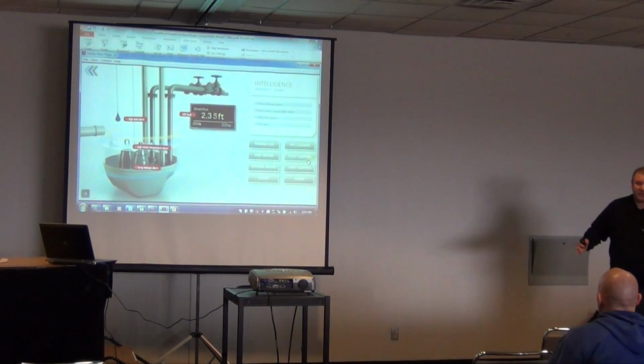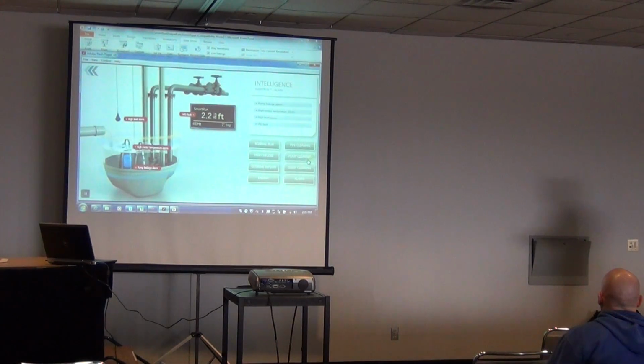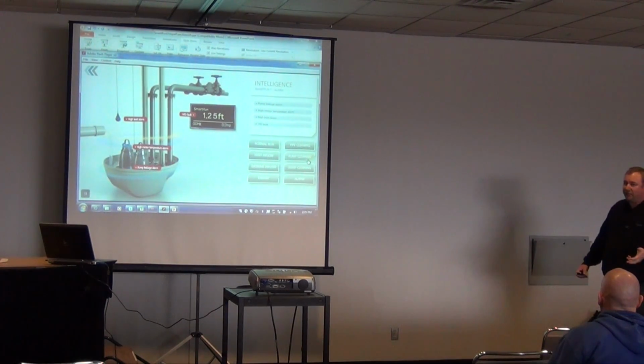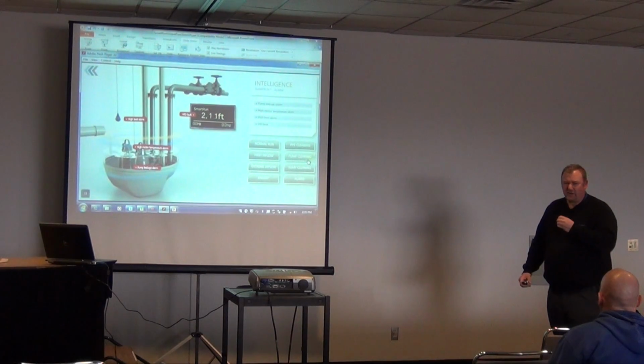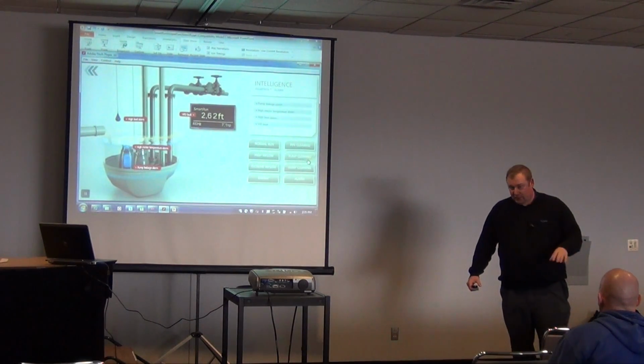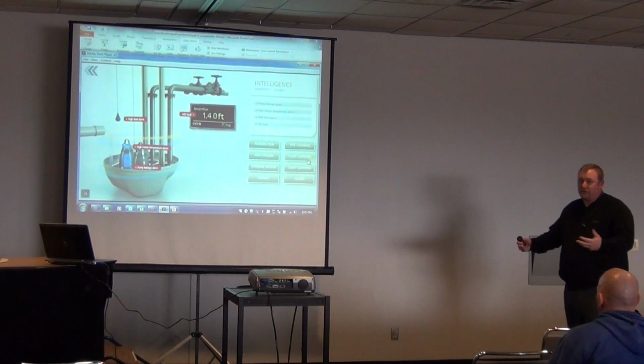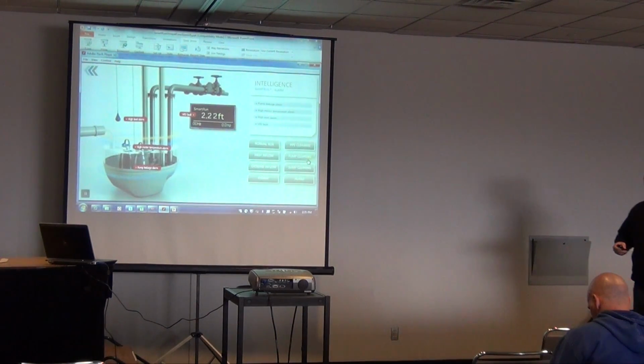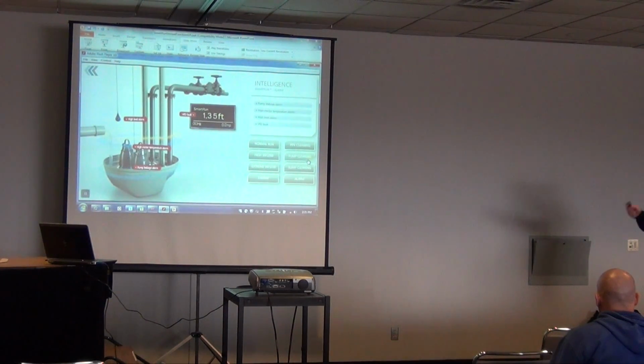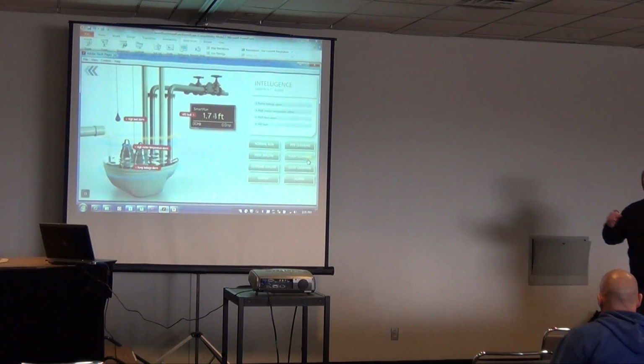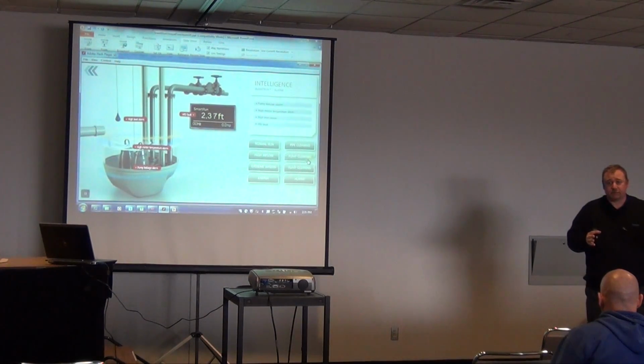Instead of a county, down south in Louisiana they call them parishes. We used Jefferson Parish, which is just outside New Orleans. It's a very wet area, lots of groundwater. They were having some issues with their pump stations, and we went in, and I really see this as a great retrofit tool. We can go in and put the controllers in, and really what we're seeing is with that 50% savings that we're saving overall, 25% of that 50% savings comes from the end technology in our pump.